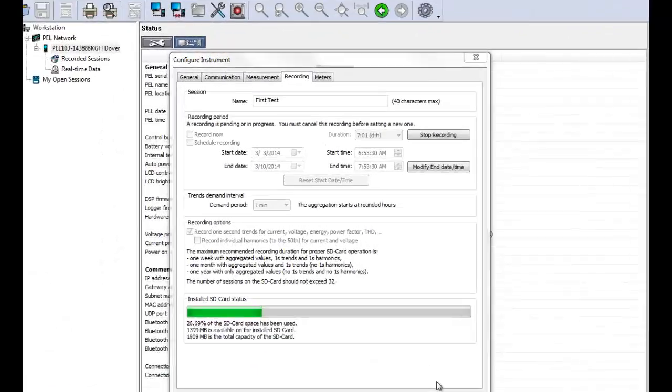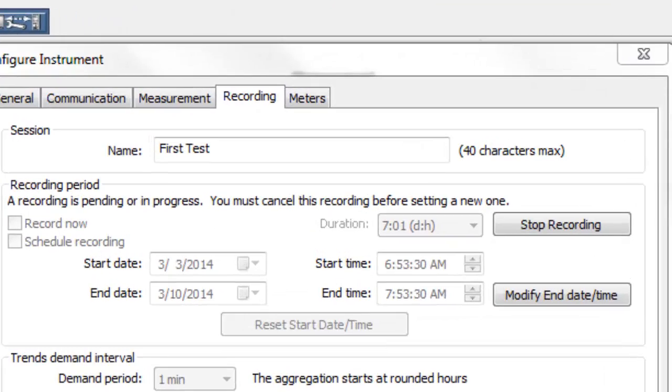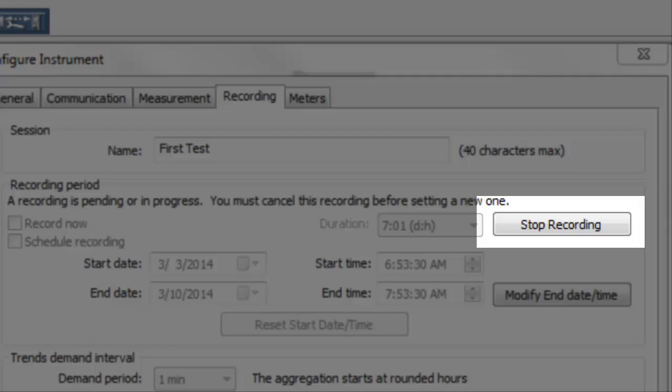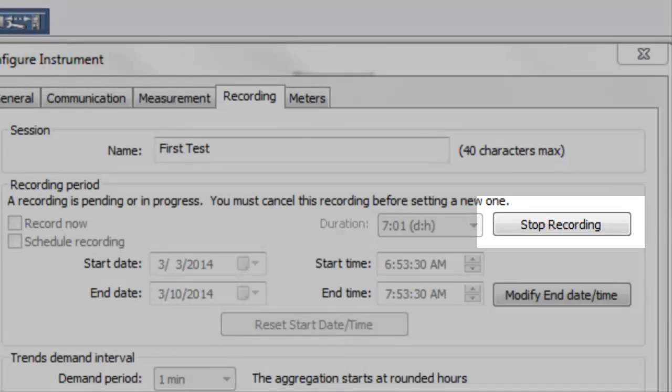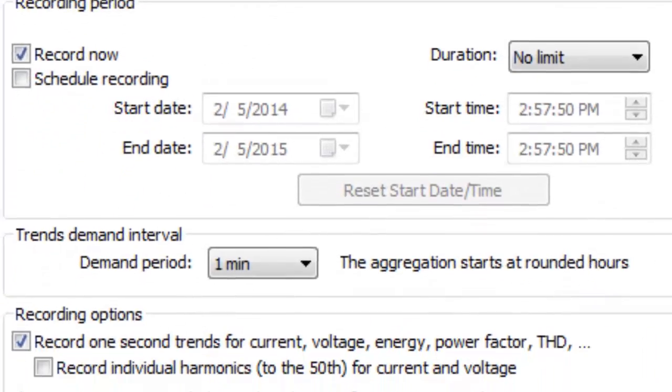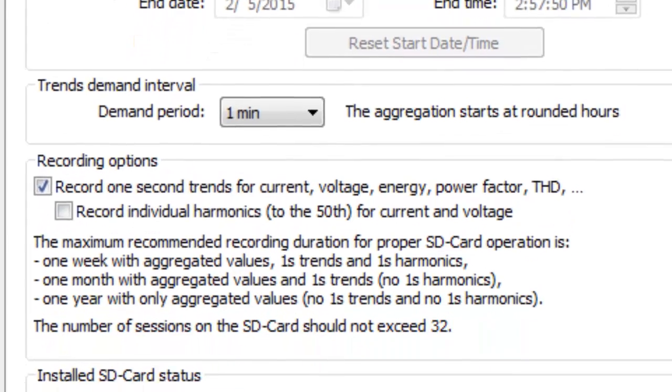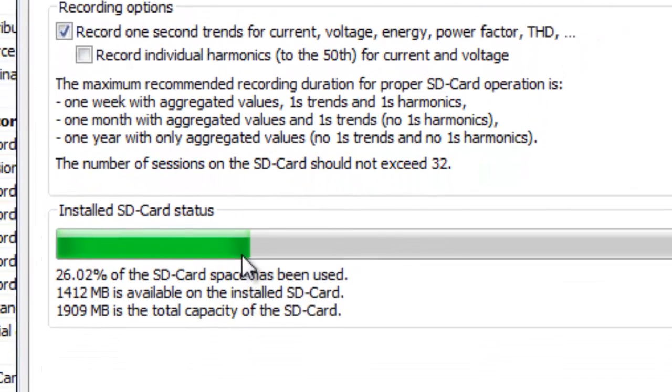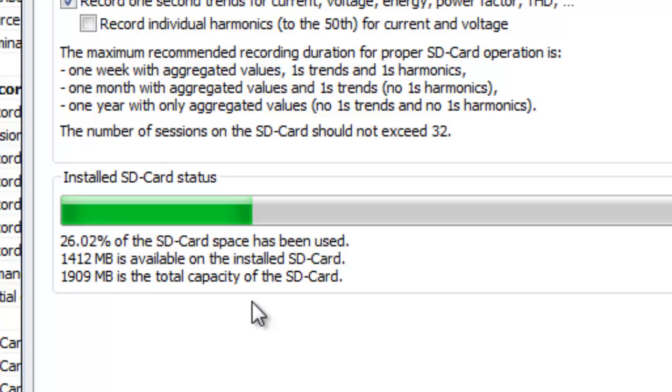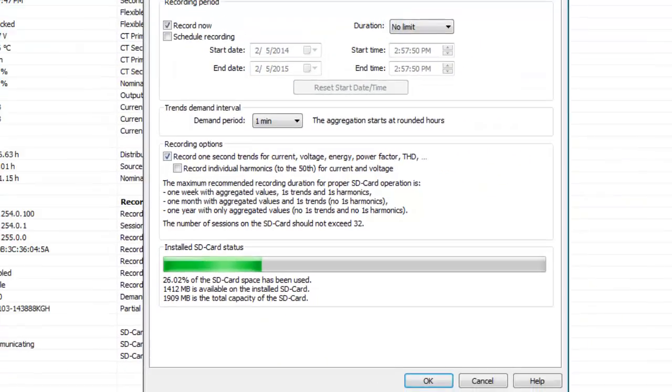While a recording is in progress, the button Stop Recording appears on the Recording tab. This enables you to stop the recording immediately. Notice the bar at the bottom of the screen labeled Install SD Card Status. This indicates how much memory has been filled on the PEL's SD Memory Card. If this bar shows that there is little or no available memory on the card, you may need to delete one or more stored recording sessions to complete the current recording.